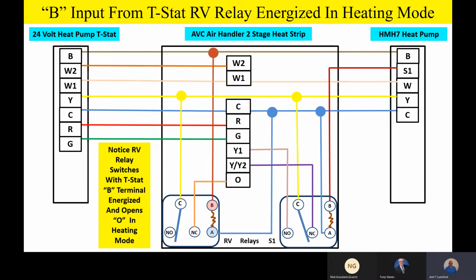So when we energize the RV relay, what we're actually doing is breaking the 24 volts going to the O signal, and that's absolutely correct. On a variable speed air handler, when we break the O signal, the air handler believes it's in the heating mode of operation, which is what we need. In the heating mode of operation, we do not want voltage on O, because that O is for cooling mode operation only on the heat pump. So any questions or comments on the relay logic, how the relays are switching, how we're going to use those relays, the S1 relay for airflow reduction, the RV relay to make and break 24 volts to the O terminal on the variable speed air handler for advanced functions of that air handler? Any questions or comments on that? No, we're good. Okay.